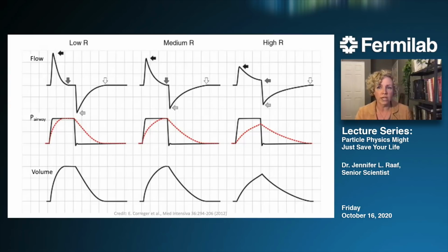In the bottom row, you're looking at volume versus time. So for low resistance on the left, you get a quick increase in the volume, and then it flattens out. As the flow slows down, the volume stops changing. At high resistance, the overall volume of air is reduced and the change in volume happens more slowly. So that curve is broadened out again.